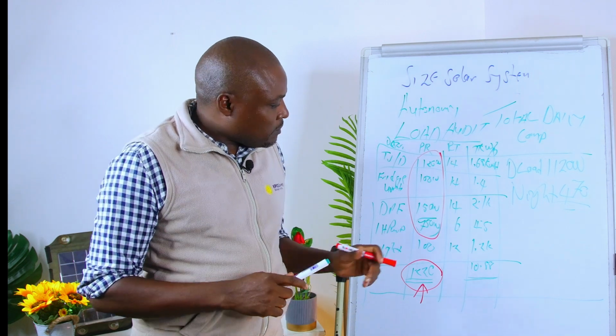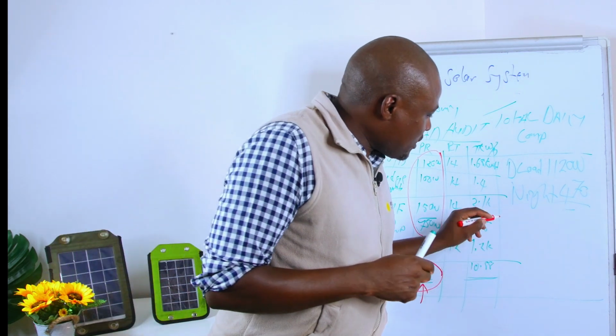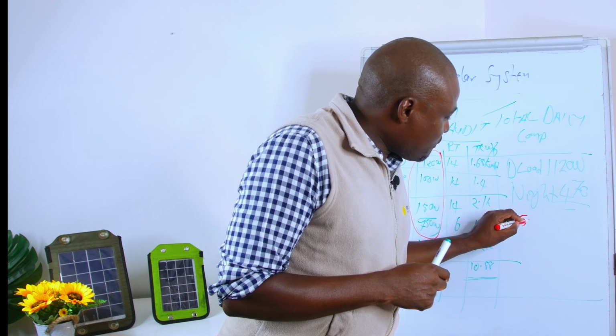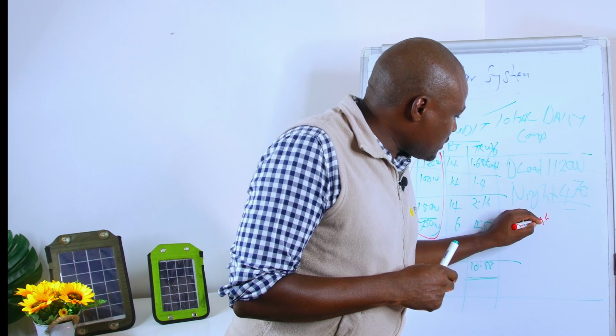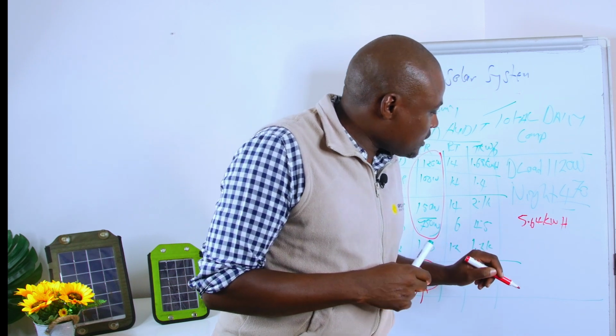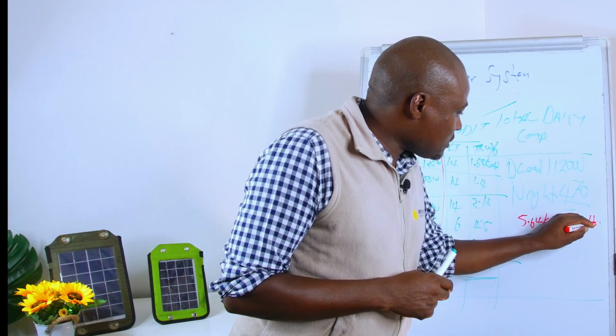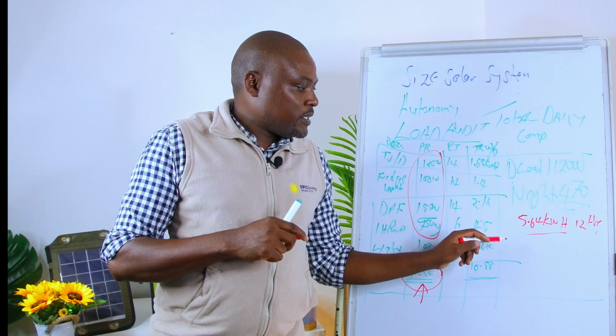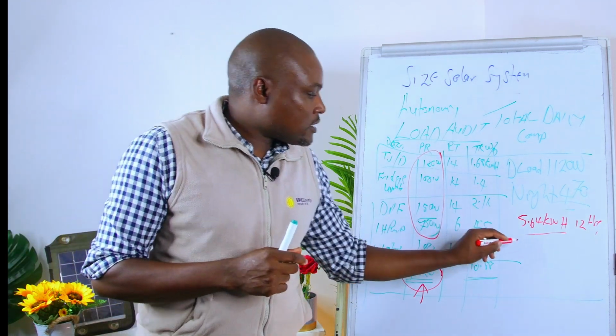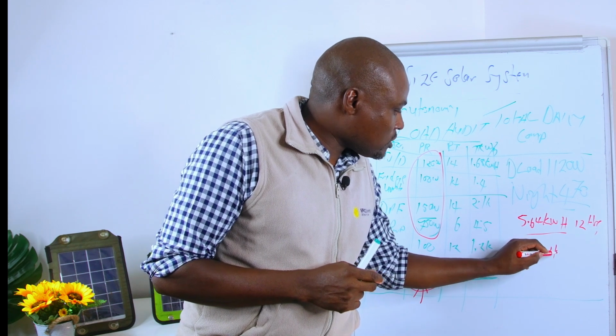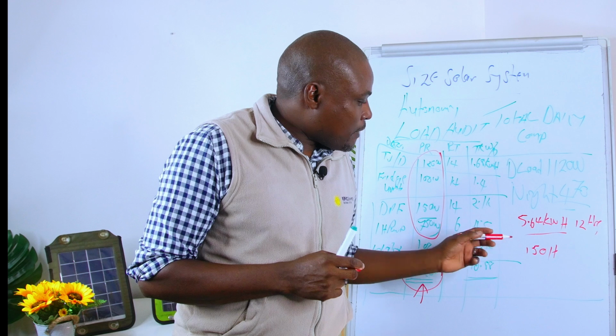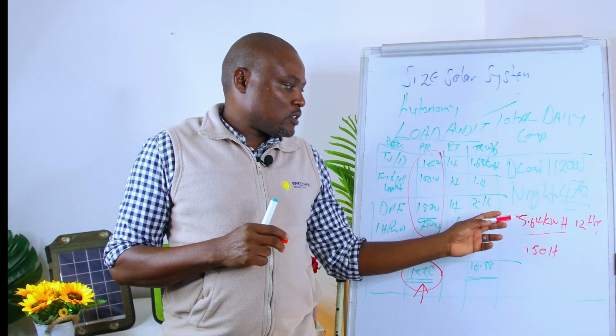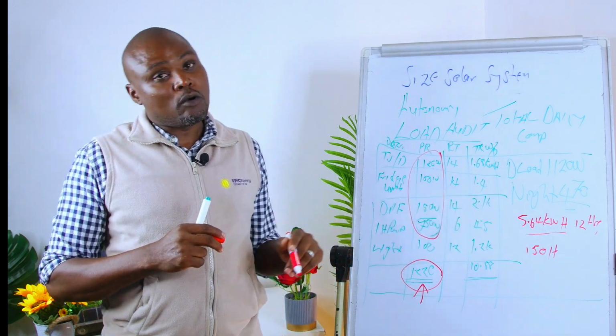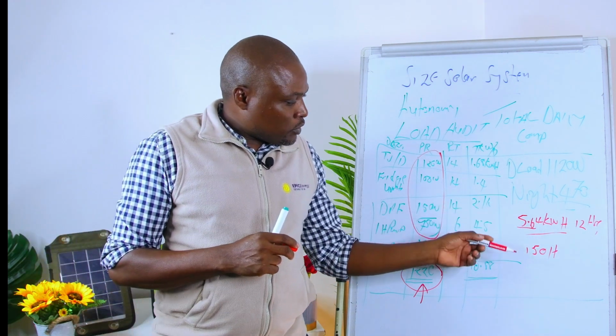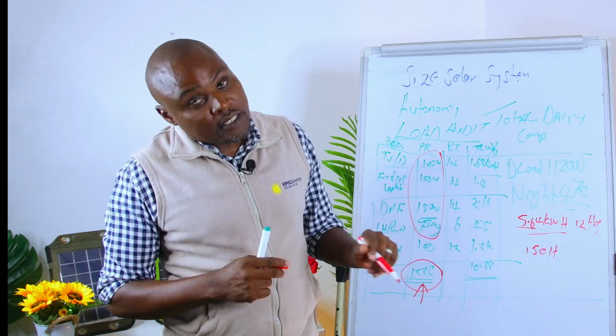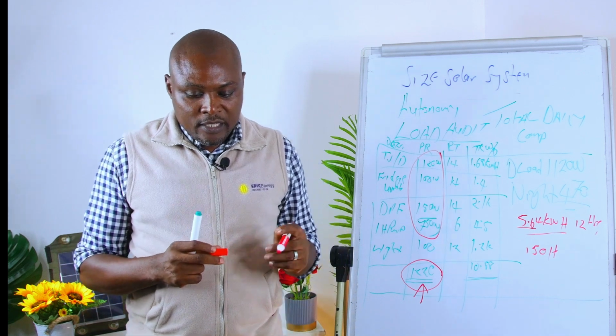So in this scenario, the battery bank, because our load here for the evening, when we calculated, I think it was coming to about 5.64 kilowatt hours, right? Based on 12 hours. So what it means is that the battery that we need for this particular system is anything around 150 Ah. We're talking of lithium in this case. 100 Ah could be smaller, because 100 Ah is going to produce for you, I think, around 4.8 kilowatt hours, which means you fall short. But because you want to give access to the client, a 150 or 200 Ah lithium battery will work in their favor in this case.